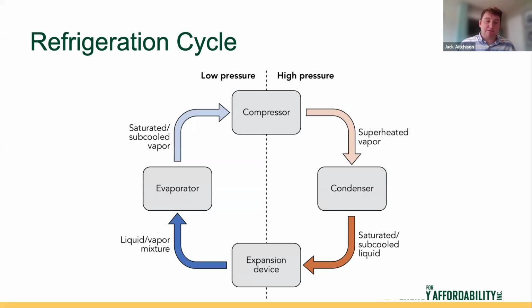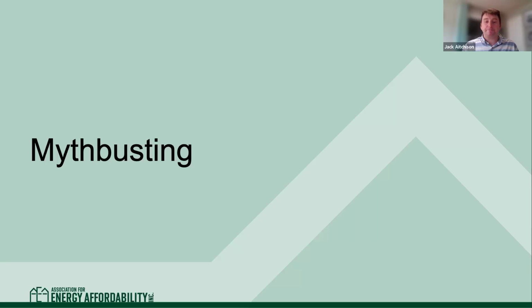So you'll see in the following slides that I'll be calling it a coil, because the evaporator can be the condenser in a heat pump. Really, it's just a heat exchanger coil, and it can reject heat on either side because it can reverse the flow of the refrigerant. Next slide, please.